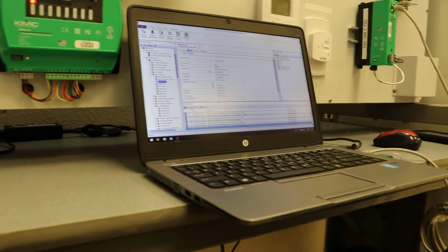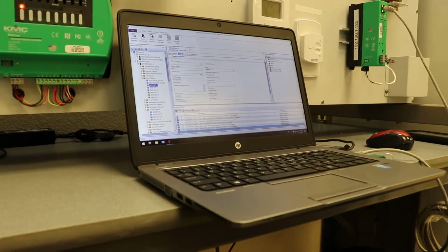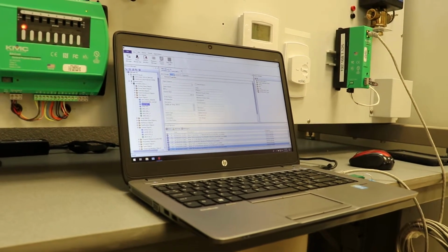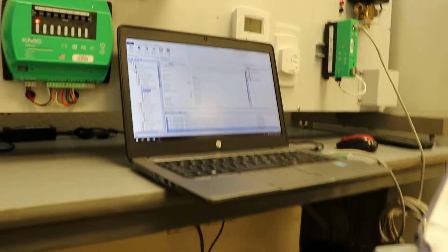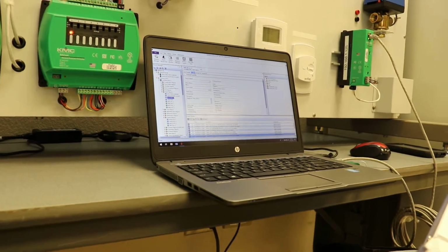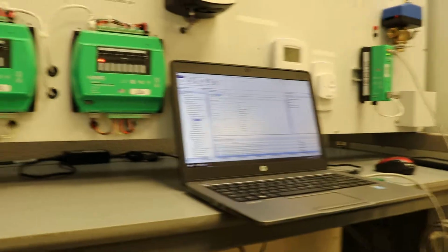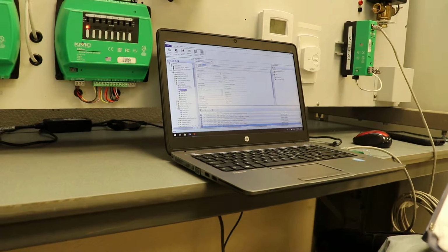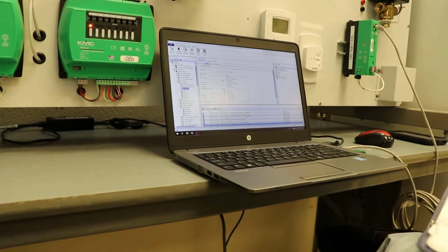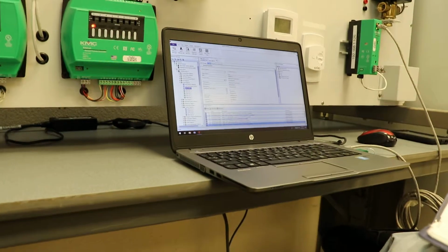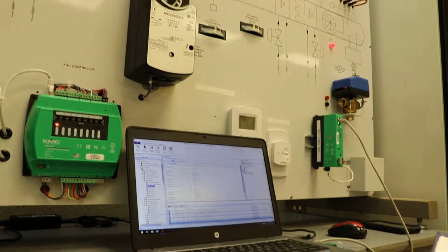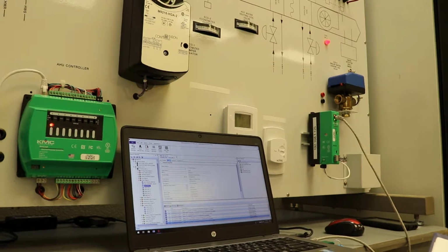Oh, okay. So it says that the heating coil valve HCV1 will modulate open and attempt to heat the air. Now, which system is this supposed to be on? Okay, so this is supposed to be on AHU1. But yeah, we should be able to step through some of these, and it should follow along pretty closely. All right. So I would suggest going through some of these and doing a little bit of it and seeing how the program operates. Okay. We may need to change a little bit of the programming, but that's something we can work through. Okay. All right. Cool.